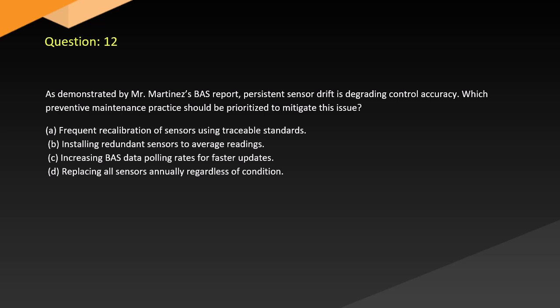Demonstrated by Mr. Martinez's BAS report, persistent sensor drift is degrading control accuracy. Which preventive maintenance practice should be prioritized to mitigate this issue? A. Frequent recalibration of sensors using traceable standards. B. Installing redundant sensors to average readings. C. Increasing BAS data polling rates for faster updates. D. Replacing all sensors annually regardless of condition.